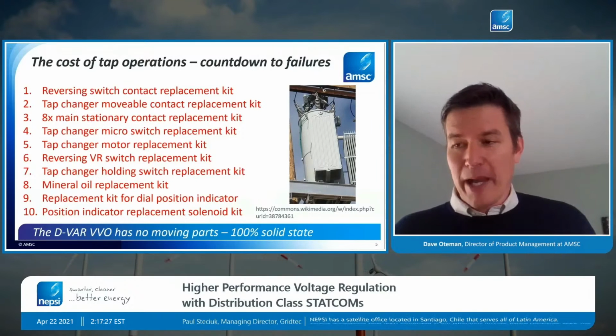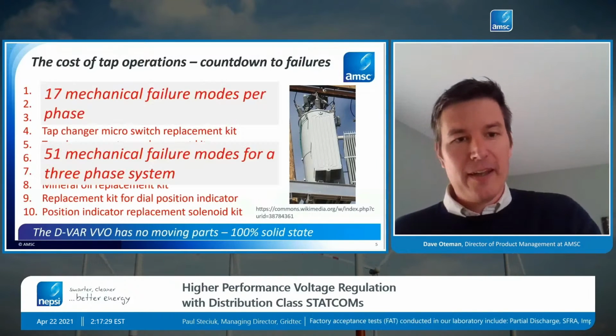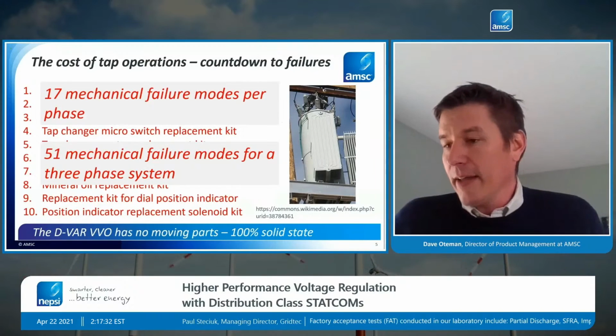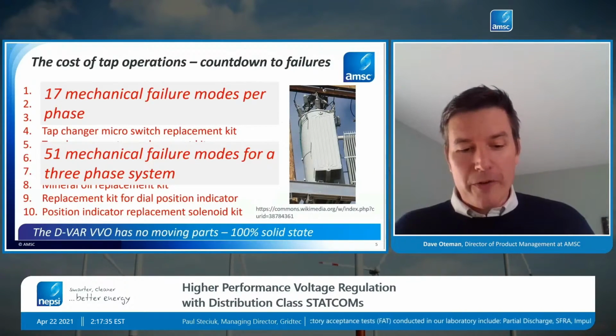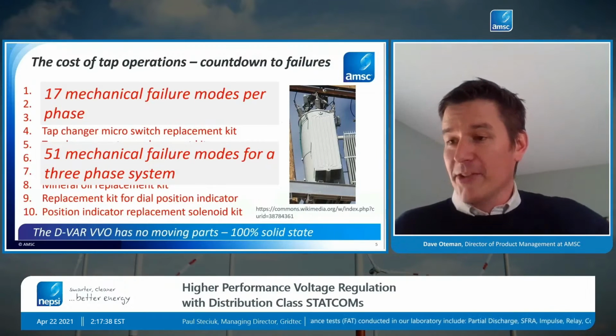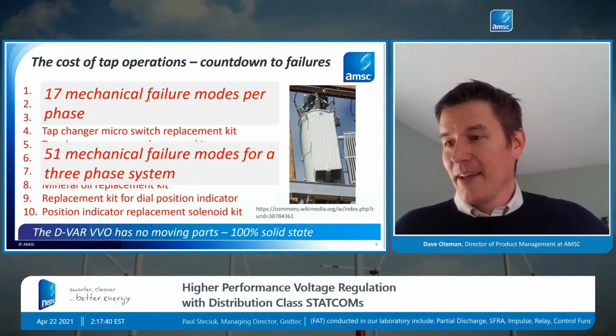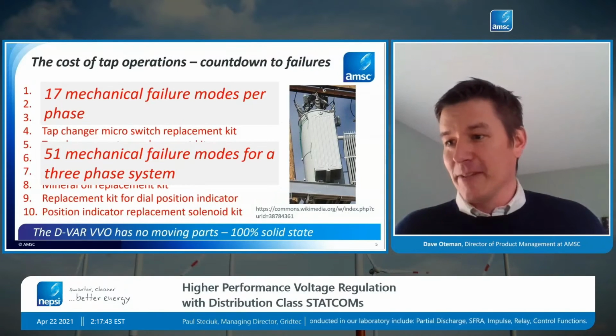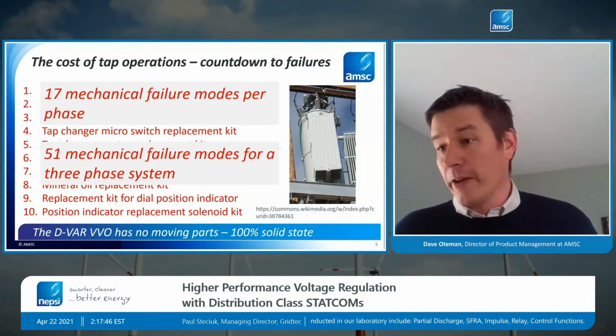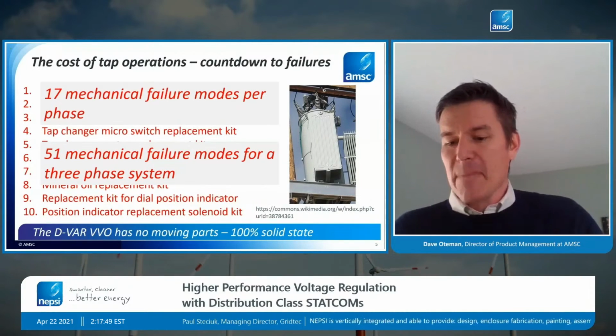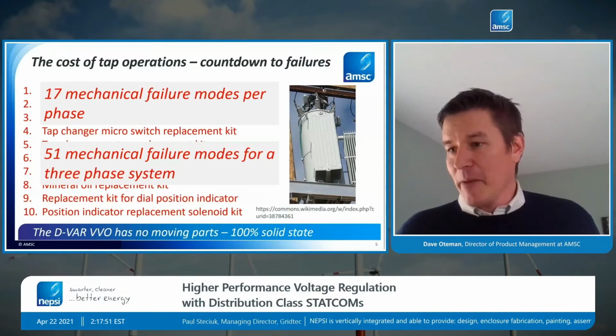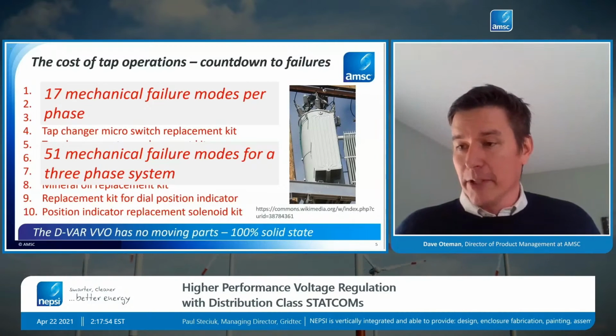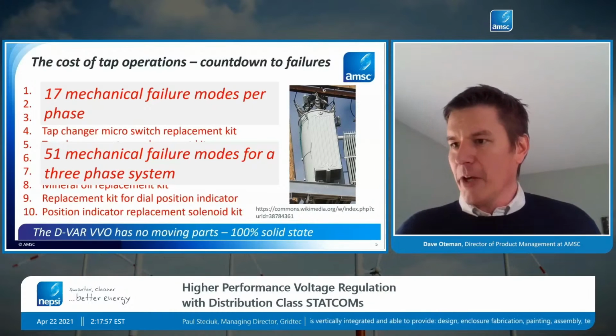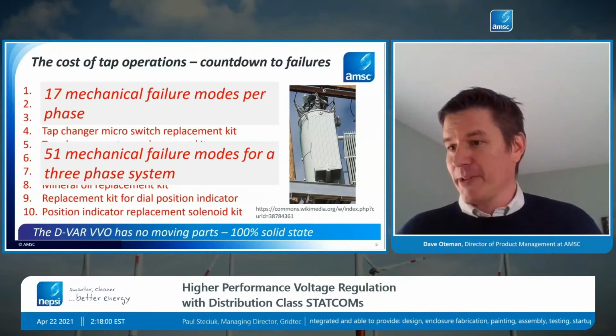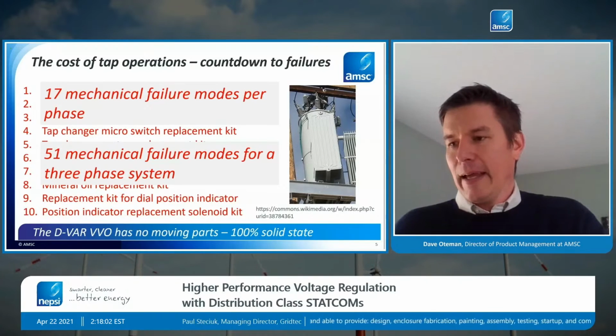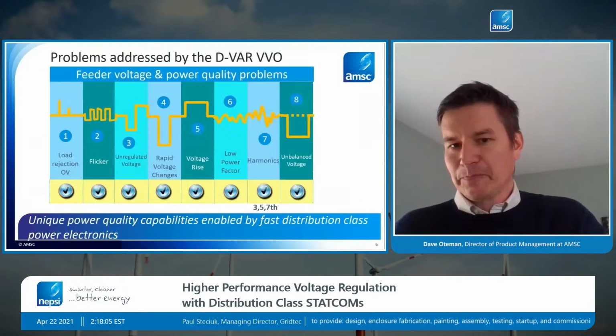Now we go to a 3-phase bank, multiply that by 3, and there are 51 mechanical failure modes in a line regulation system. Every single one of them will be accelerated with additional operations on the equipment. So this equipment is not a match made in heaven for more variable generation, and it's one of the things utilities need to address now moving forward. As I mentioned, the power electronics advantage is that we have literally no moving parts in our D-VAR VVO solution. It's 100% solid state power electronics, no mechanical failure modes to deal with.